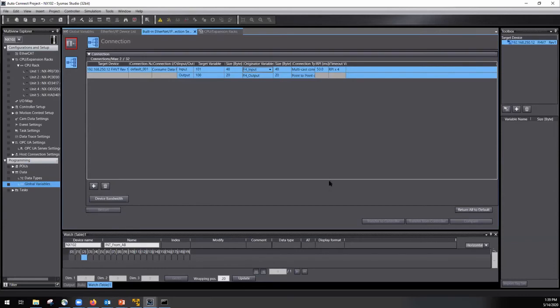that's the idea anyways. Load the EDS file, make a connection with the device, and then it tells you what instances are available and the size of the instance according to the EDS file, and then you simply make your tags and transfer it to the controller. Any questions?